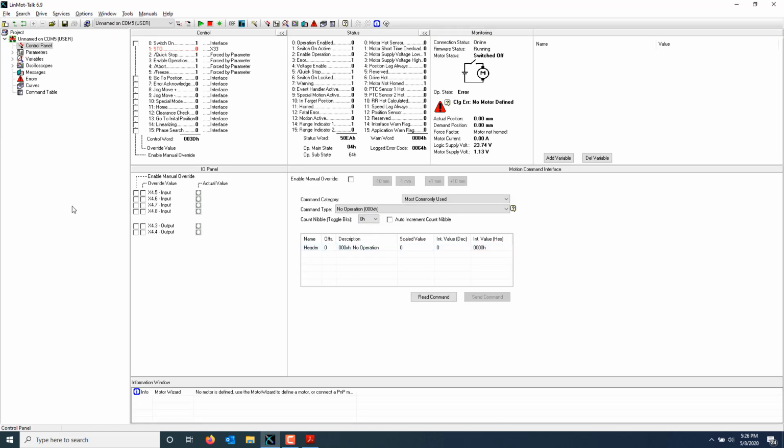If firmware installation does not complete successfully, but your drive is running firmware version 6.8 or newer, you can take advantage of the drive's ROS, or remnant operating system, which is only installed once and is left intact during firmware installation. It is therefore preserved in the event of corrupted firmware. Please note that this feature is only available in LinMot talk version 6.8 and newer. You can use the wait ROS script to use the ROS to recover the drive.